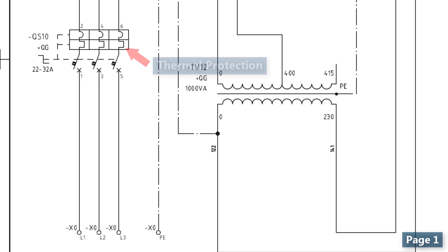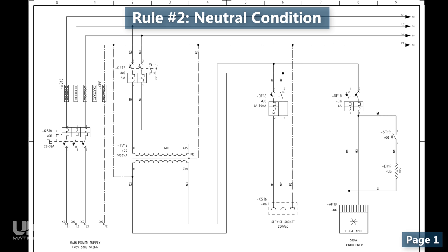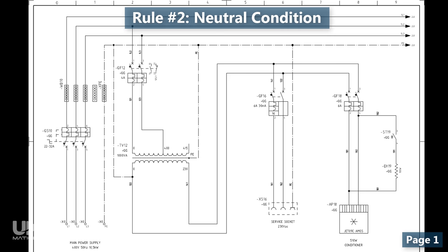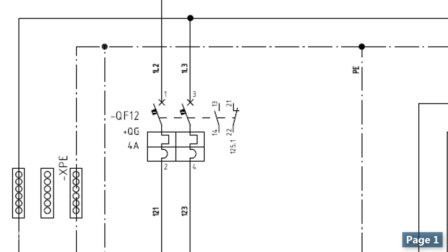From these terminal blocks, we move on to a three-pole circuit breaker with thermal and short-circuit protection capability. As another rule of thumb, the wiring diagrams are drawn in the neutral condition, meaning that all of the contacts, contactors, circuit breakers, etc. are shown in their normal or non-energized condition. Therefore, this contact is closed because it is a normally closed contact and the rest of the contacts are open. We have a great video about NO and NC contacts and their actual application examples that you can watch using the link in the description if you wish.